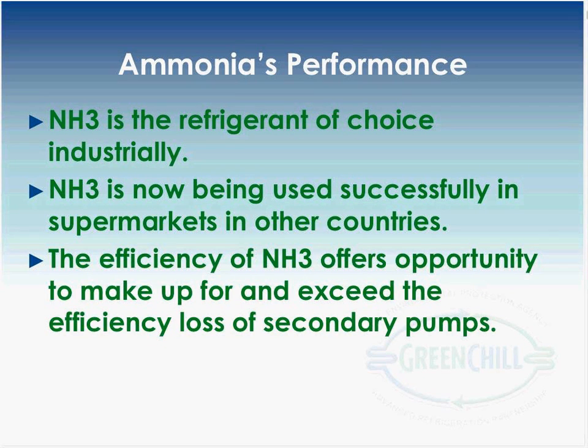Moving on to ammonia's performance—it's the refrigerant of choice industrially. I hate to use that word, because as a fellow commercial retail refrigeration engineer, we know industrial systems are completely different from commercial systems, but it's still important to show. Some industrial systems use anywhere from 50 to 200,000 pounds of ammonia, and you're not just going to put any refrigerant into systems that large—it has to be a proven refrigerant, a proven technology.